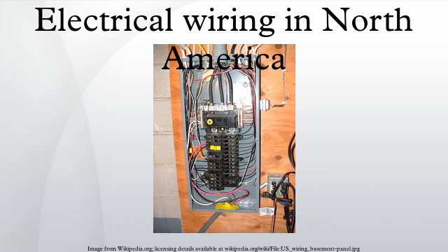In 240-volt applications not requiring a neutral conductor, the white wire may be used as the second hot conductor, but must be recolored with tape or by some other method. For wire-flexible equipment, connection cords have red as the fourth color. Unlike older European practices, color coding in flexible cords is the same as for fixed wiring.